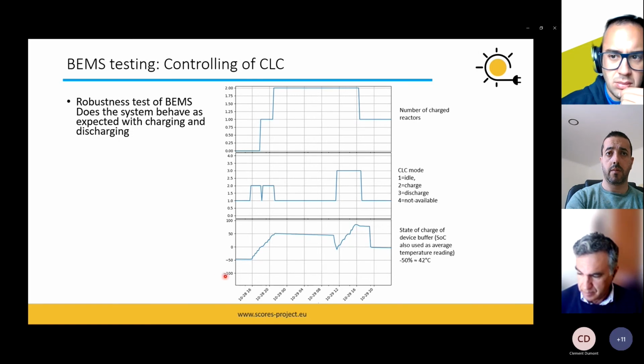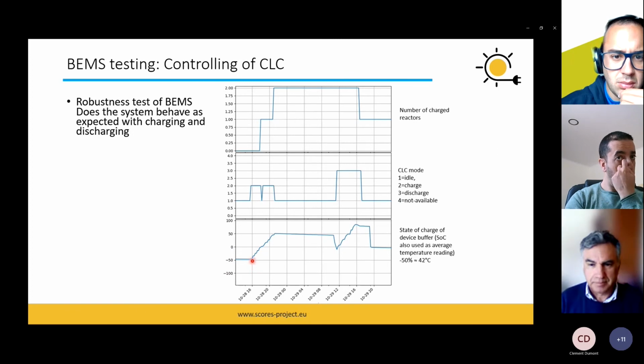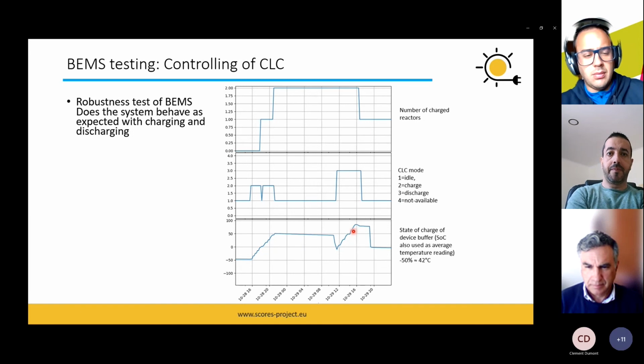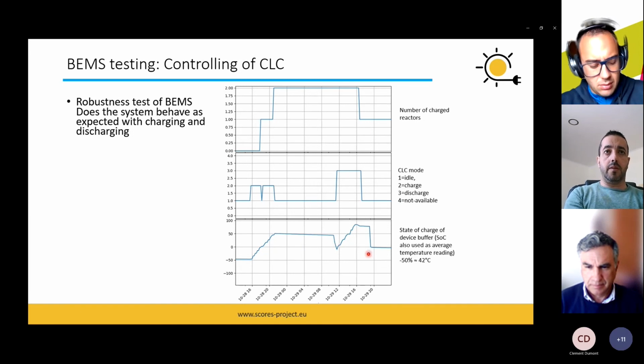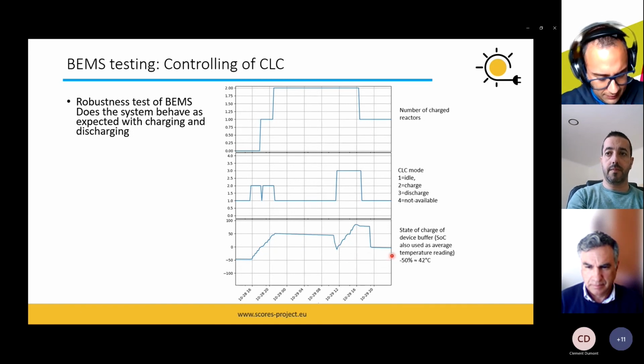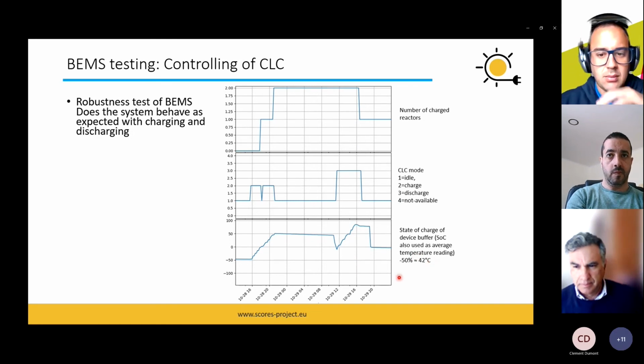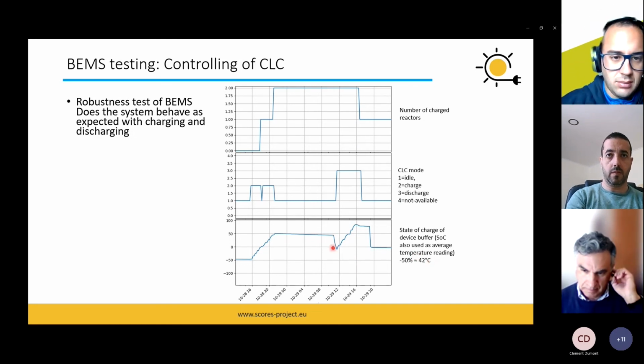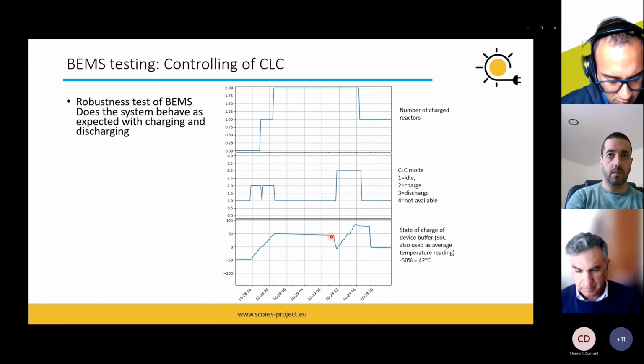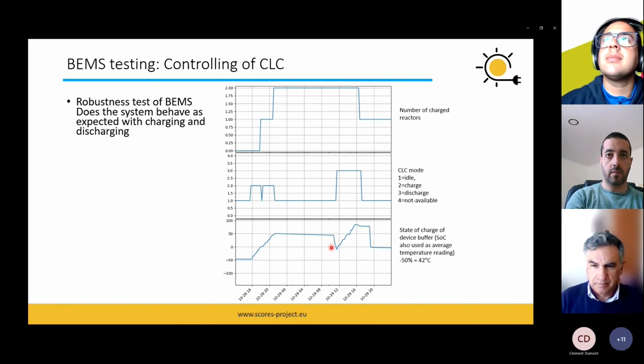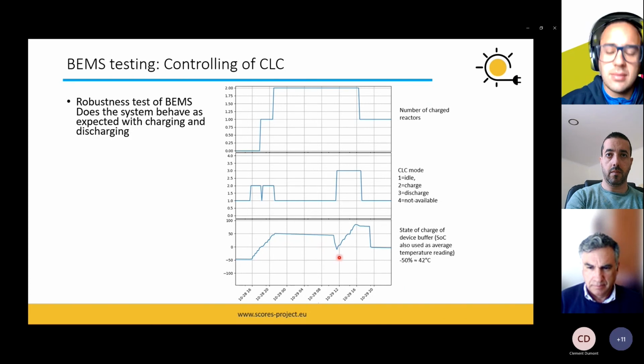During both charging and discharging, energy is released, so you see two increases of energy in the CLC buffer. Because discharging especially requires the buffer temperature inside the CLC to be below 42 degrees, we had to dump energy from the CLC buffer into the storage buffer before the system could get started.